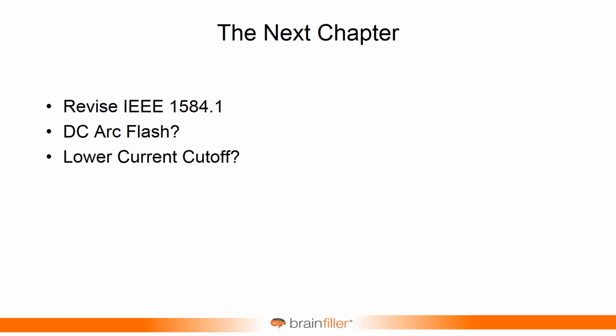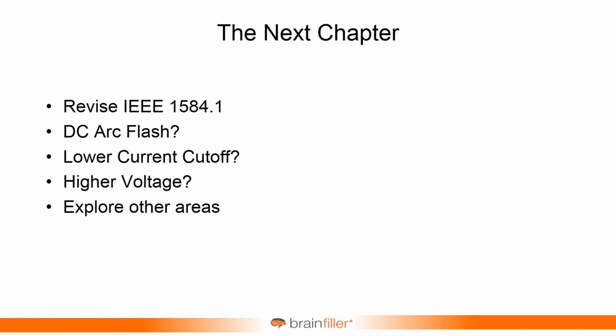Are we going to be able to work with that anymore? I'm not sure. Because the problem with trying to come up with a low current cutoff, as I said, it's not a hard, fast number. There's the possibility under certain enclosure sizes, certain configurations, and smaller gap distances, you could sustain to some really low values. So that one's kind of up in the air at this point. Higher voltages, that's something that we've talked about. The standard goes up to 15 kV. Maybe someday we'll be able to take it above 15 kV. Who knows? Stay tuned. And then many other areas. There's just so many other areas.